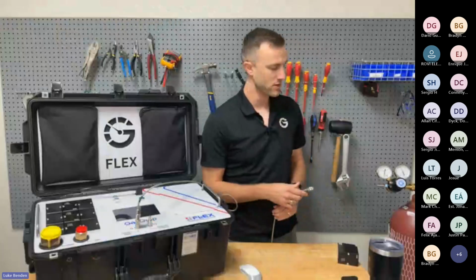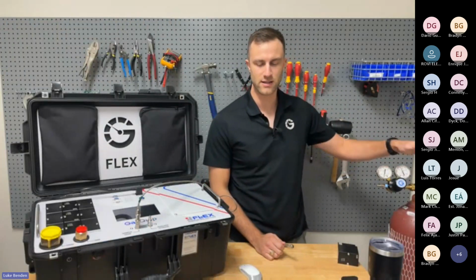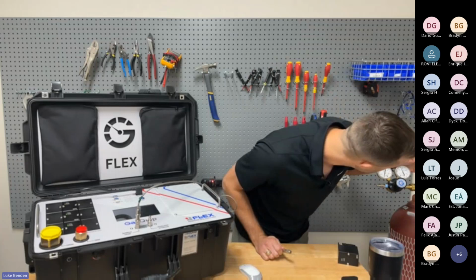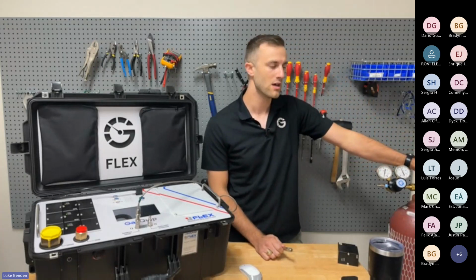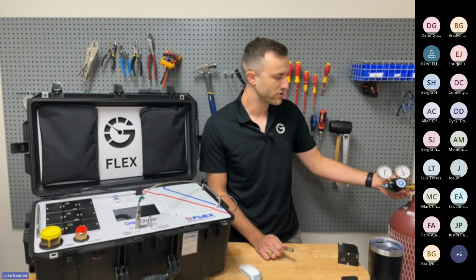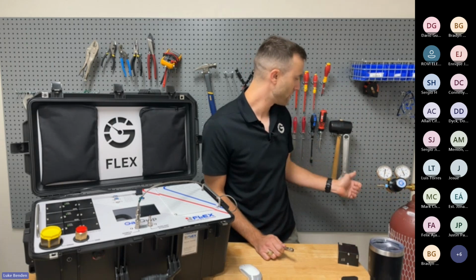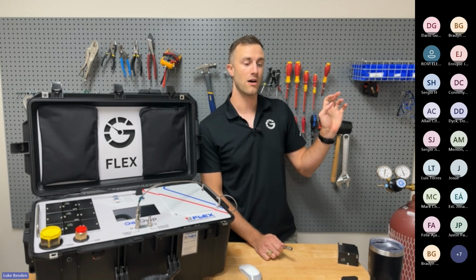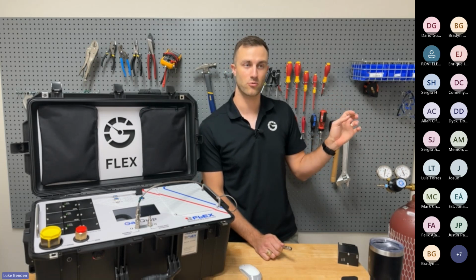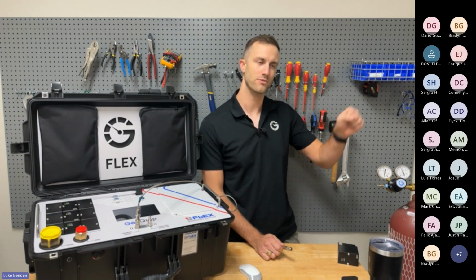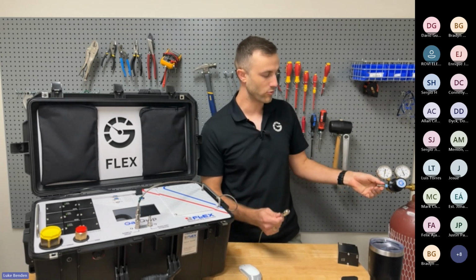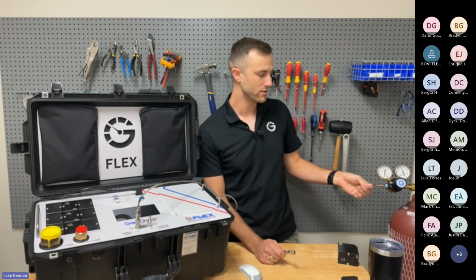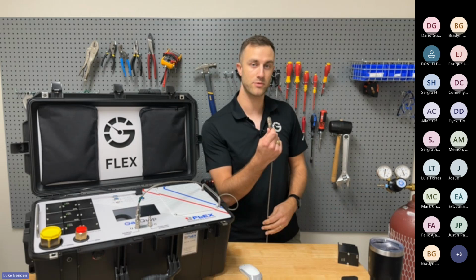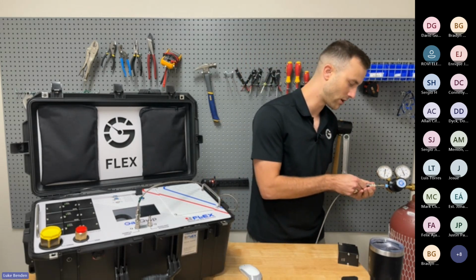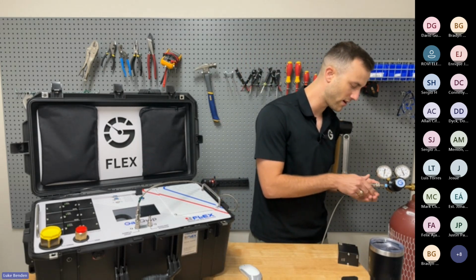Let me get back to the scene here. So we've already connected up our regulator. This is a high pressure cylinder reading about 310 PSI currently. We've already connected up our cylinder regulator with our wrench and snugged it down. It's a CGA 590 connection, so it's opposite of a nitrogen, so it's righty loosey, lefty tighty. So we'll tighten that up. We've got a Rectus Type 21 male on this, and we can connect that right up to our sample hose. All you do is pull back the collar on that and just shove it on there.